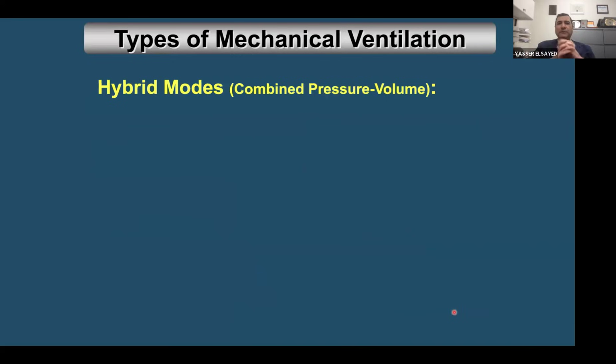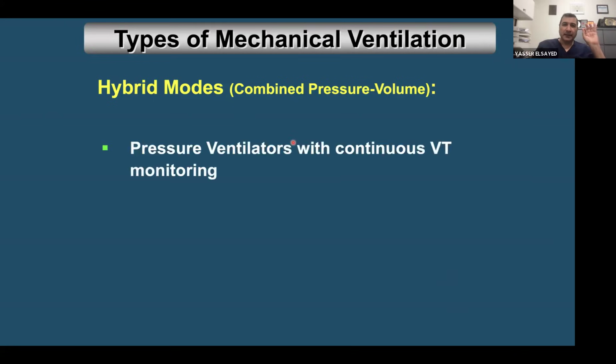So hybrid mode, let us now focus on the mode that we are using. Regardless, we are using Servo, which is one of the new ventilators now we are using with NAVA in a lot of centers in North America, or if you're still using Draeger 500 or whatever ventilator that you are using with the hybrid mode, combined pressure and volume. So this is not a volume limited ventilation. That's one of the misconceptions of a lot of our colleagues. That's not volume limited. That's hybrid mode. It is pressure limited, and with the volume hybrid that might deliver a preset volume but variable pressure. And let us understand that more.